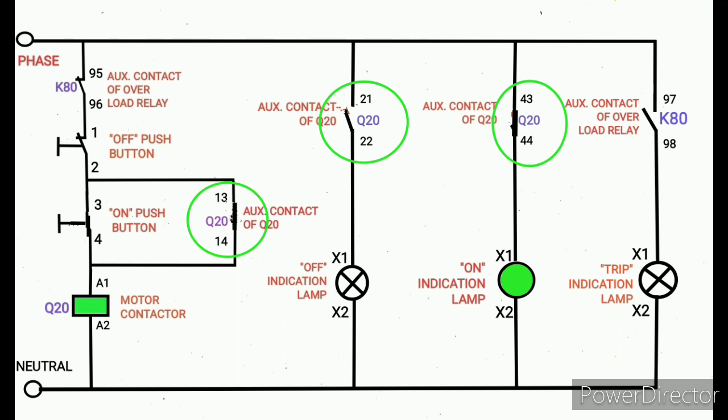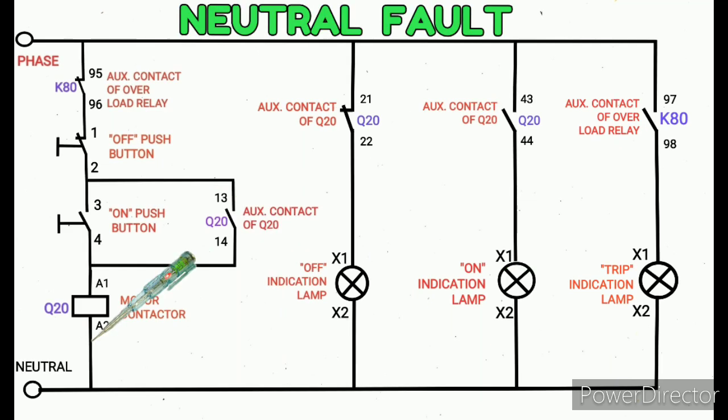Then auxiliary contact of 43-44 changed to NC. Now I completed the phase side of testing. I am going to explain the neutral side. Neutral end, you put the tester on the neutral point of any area. You need to check with the neutral.